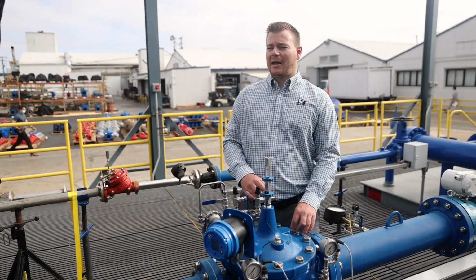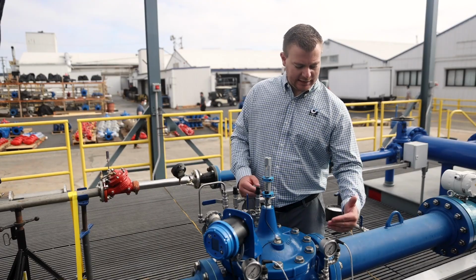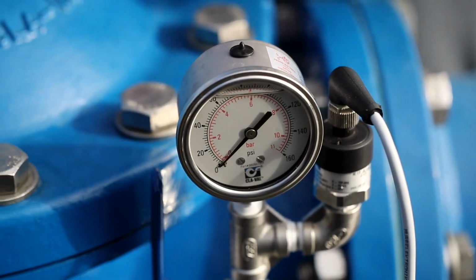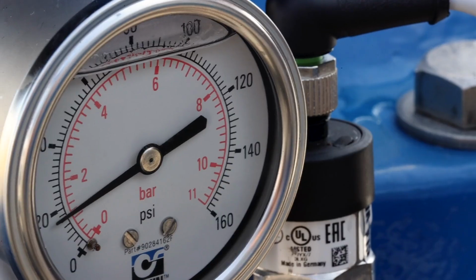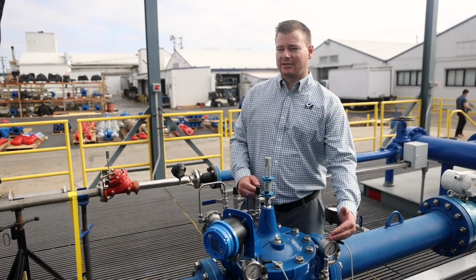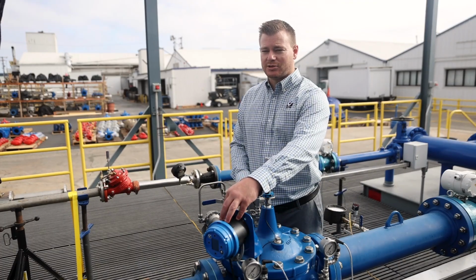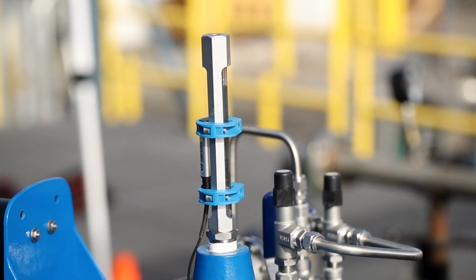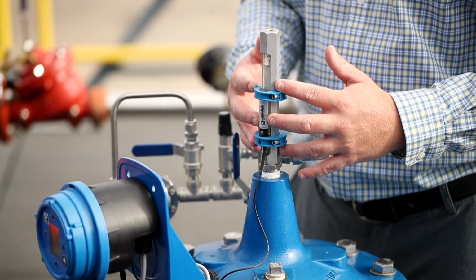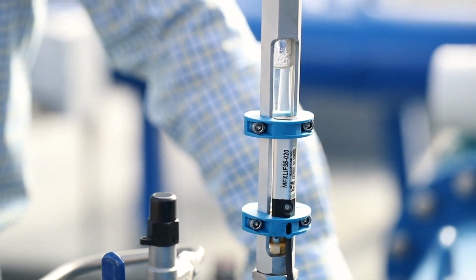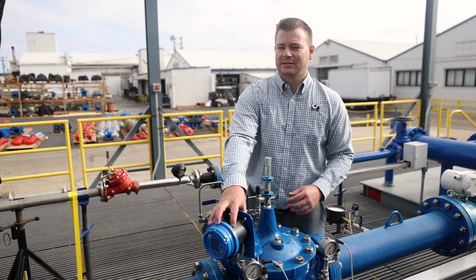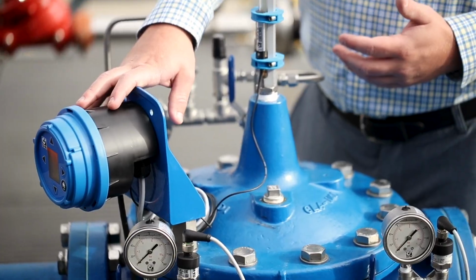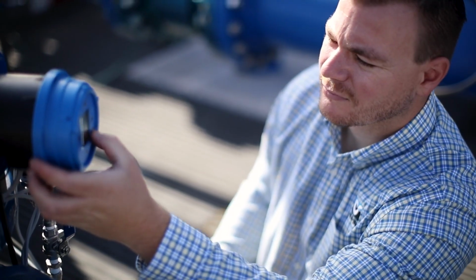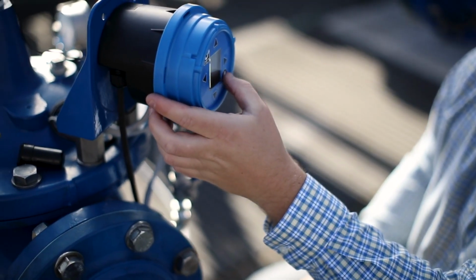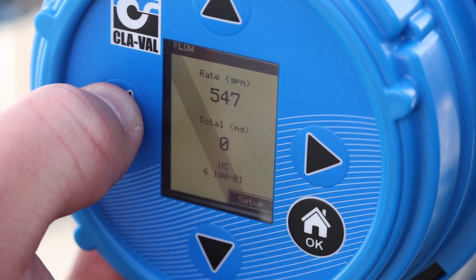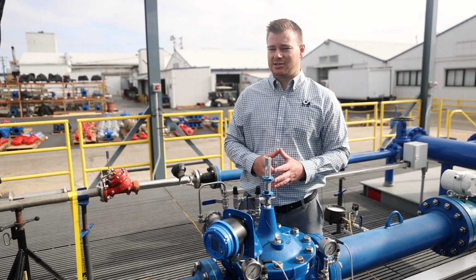The XP2F package includes an inlet and outlet pressure transmitter, the Cla-Val X141 PT, which uses a factory standard 4-to-20 signal back to the flow module. We also have the X117H position transmitter, which also uses a 4-to-20 signal back to the flow module. And the final component is the X35 flow module, which takes all that information in and outputs the flow as a 4-to-20 value that can be sent to the SCADA system for flow indication.